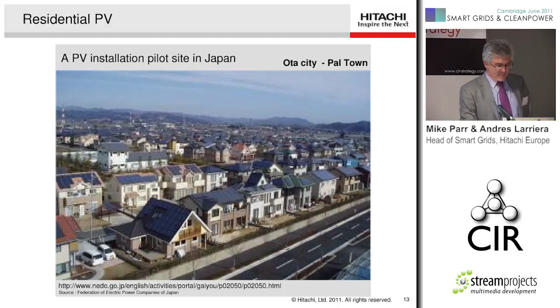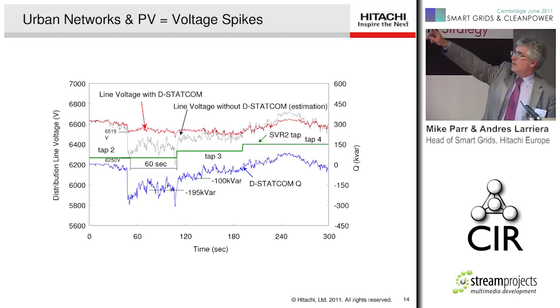This is not some kind of theoretical construct. If you look at the black line, on the far left, you can see it's just a little bit above the 6,600 or 6.6 kV point - that's nominal HV or MV volts in Japan. If you go along that black line, suddenly you can see it drop down. That's when you get a cloud or a couple of clouds going over the sun. Suddenly, instead of all the panels producing power that's consumed locally, they're not, so suddenly the local transformer's got to produce the power, and you get a big drop in volts.